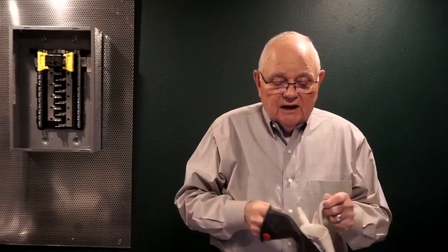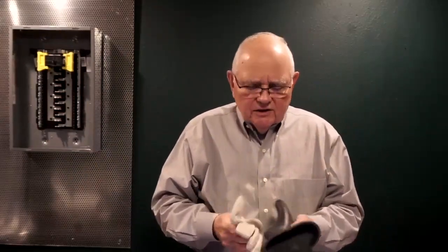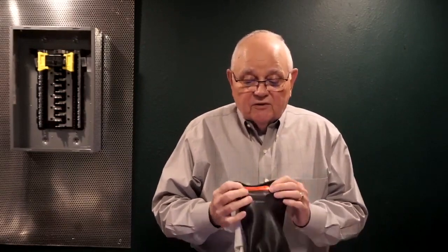Now, rubber gloves, they have to be tested and inspected daily before each use. If you don't know how to do that, then you need to get some training on that, because we have to check the dates, we have to check the fit, we have to check the cleanliness, we have to do an air test on it and so forth, as well as check the leather protectors. So that's a good topic for a safety meeting for you right there, is to have someone go through how to do a test on a rubber glove.